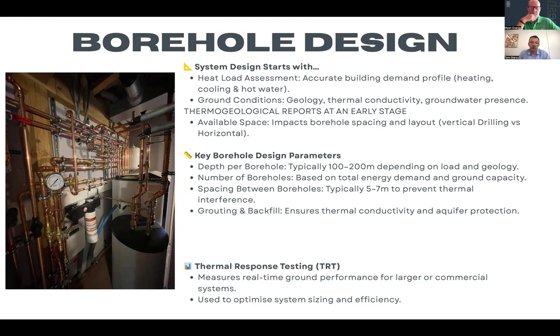So we would normally do them between 100 to 200 meters, but that depends on the load and geology. If we know we are in chalk, we might drill boreholes deeper because they are more efficient. But if we know we are drilling in sand or running sand, we might avoid this area because they can provide a bit more problems with the sand collapsing. If that's the case, the driller would have to case the borehole to a certain depth to reduce the risk of collapsing and be able to insert their probe to the required depth. And after that's been done and grouted, the casing comes out and the borehole collapses and is fully working.